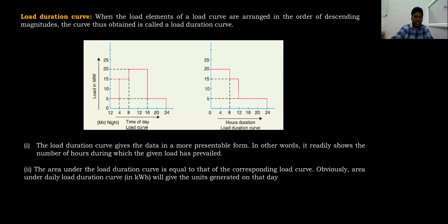Similarly, the load duration curve. The load duration curve is derived from the load curve, and it is similar to the load curve. Say for example, this is a load curve, with time and megawatts given. You see here from 8 to 16 you have a load of 20. In the load duration curve, in order to get the time of maximum load, we need to redraw the load curve. Here 8 hours you have a load of 20 megawatts. You see 0 to 8, total span is 8 hours, 20 megawatts you have.